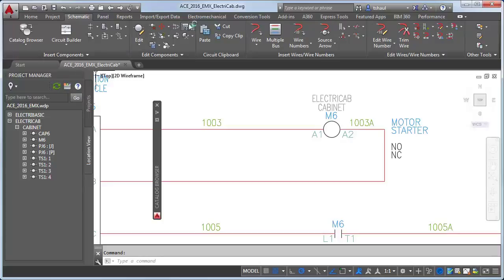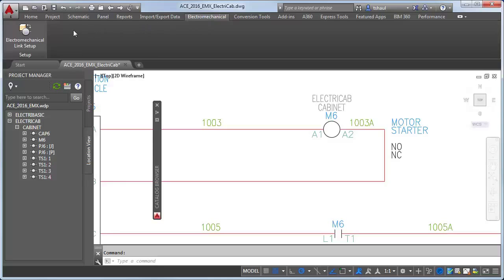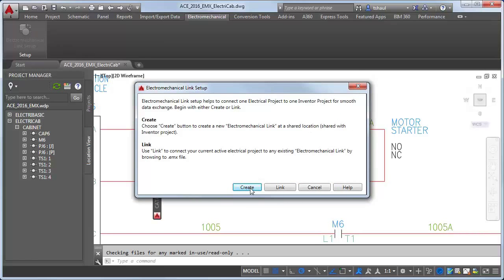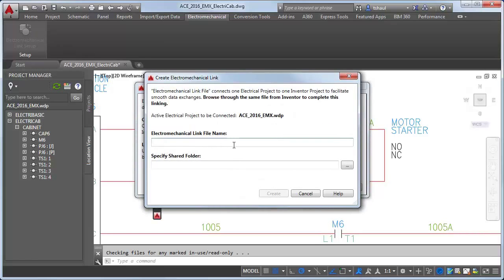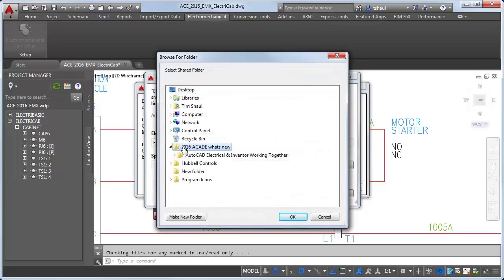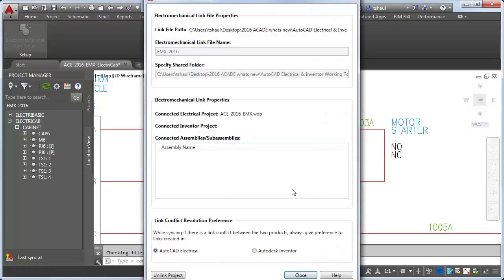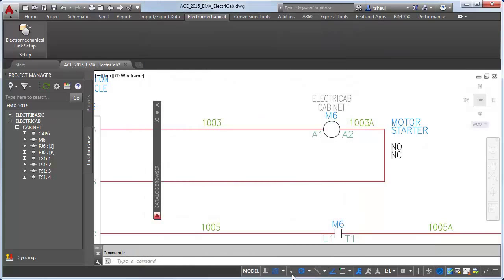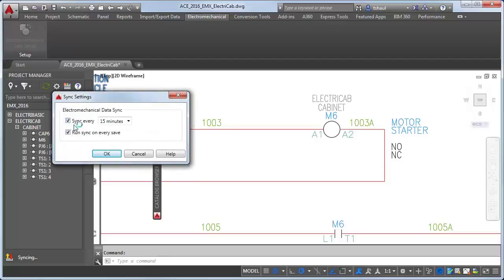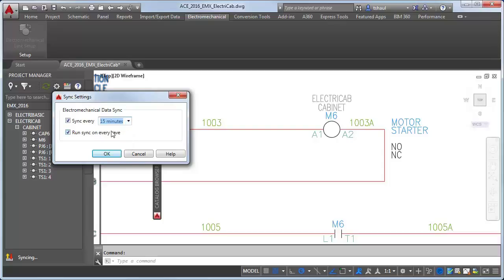The location tab includes standard components, terminals, PLC modules, and cable markers. In the Electromechanical ribbon, we will continue the design process with the electromechanical link setup, establishing a live link between AutoCAD Electrical and Inventor cable wiring harness. Use the link conflict resolution options to specify which data is preferred when there is a link conflict during the sync operation. The sync settings can be configured to update at determined intervals of time, at file save, or can be run on demand.